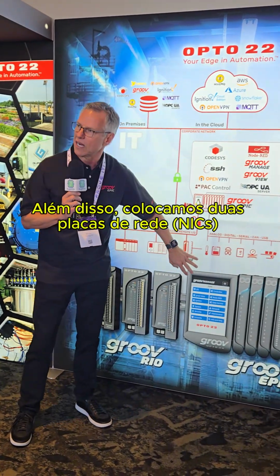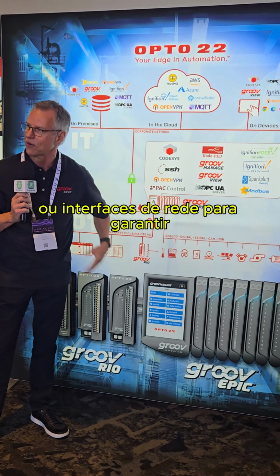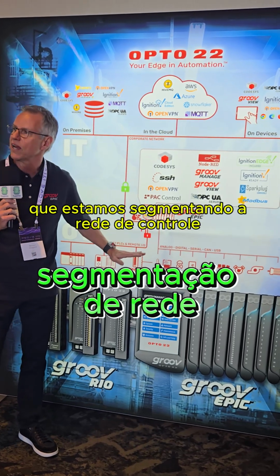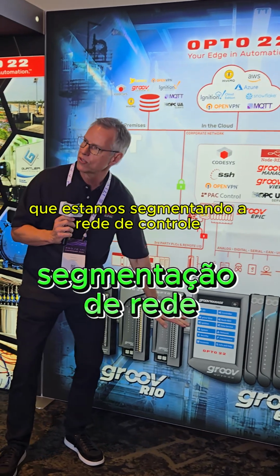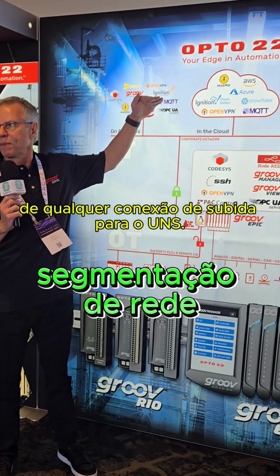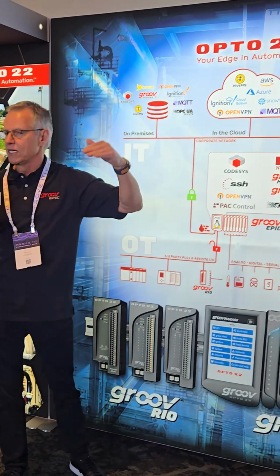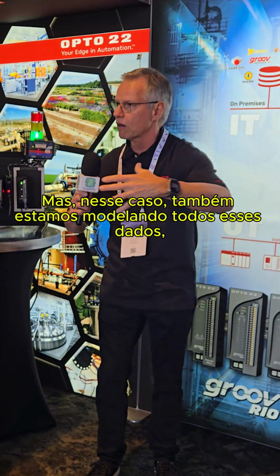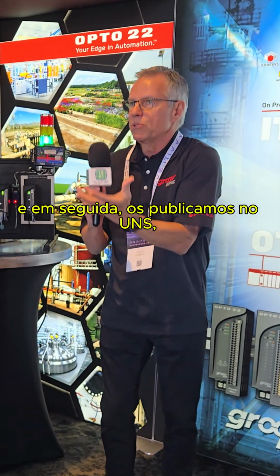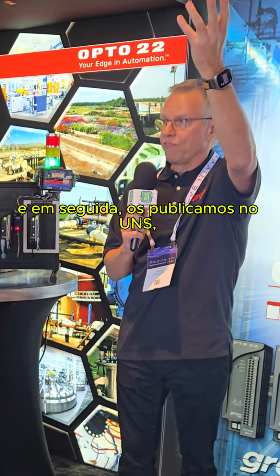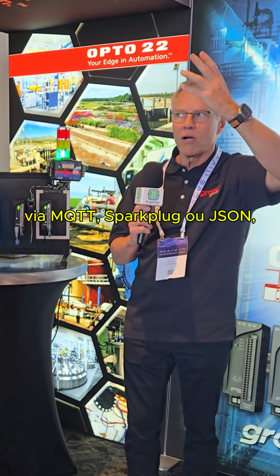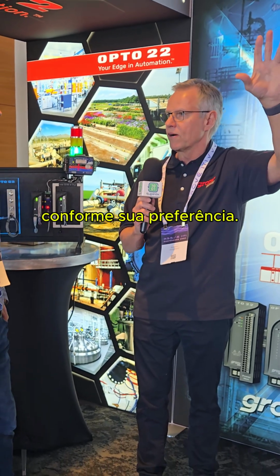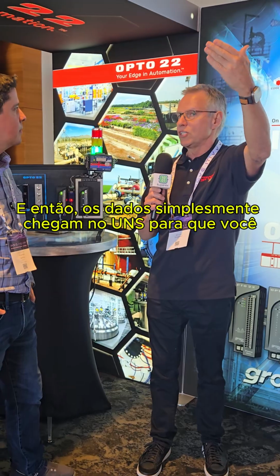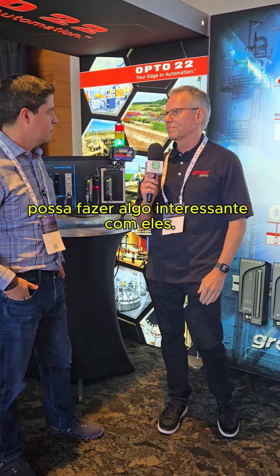And we put on dual network NICs or network interfaces to make sure that we're segmenting the controls network from any northbound connections to the UNS. In that case, we're also modeling all that data, and then we're publishing it up to the UNS via MQTT, Sparkplug, or JSON, whichever you prefer, and then the data just lands in the UNS for you to do something interesting with it. Very good.